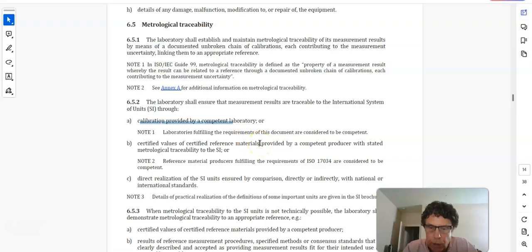as it pertains to calibration. So this is where the term calibration starts getting fuzzy, and you're like, well, I don't calibrate the ICP-MS. Well, actually, you do check the measurement traceability of your ICP-MS, so you are meeting the requirements of calibration.